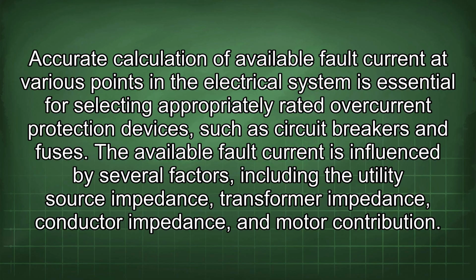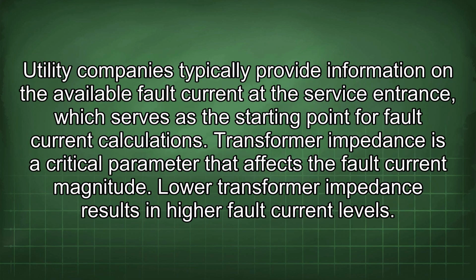The available fault current is influenced by several factors, including the utility source impedance, transformer impedance, conductor impedance, and motor contribution. Utility companies typically provide information on the available fault current to the service entrance, which serves as the starting point for fault current calculations. Transformer impedance is a critical parameter that affects the fault current magnitude. Lower transformer impedance results in higher fault current levels.